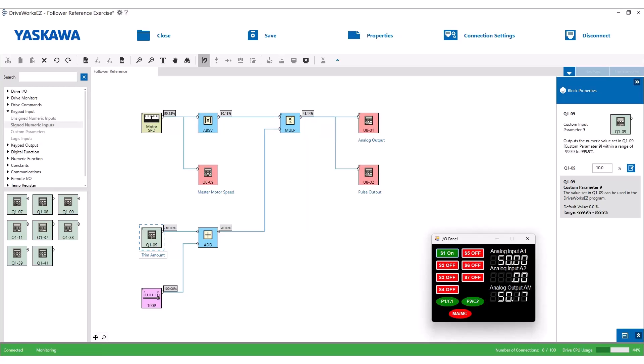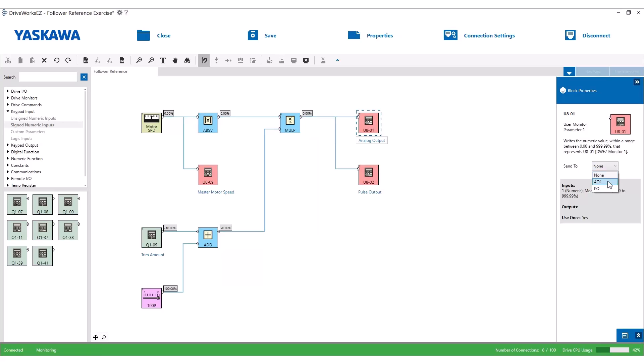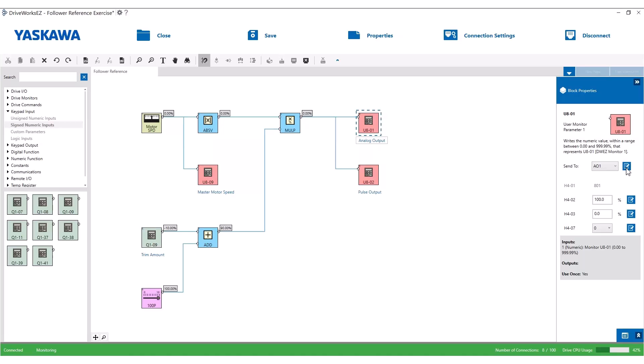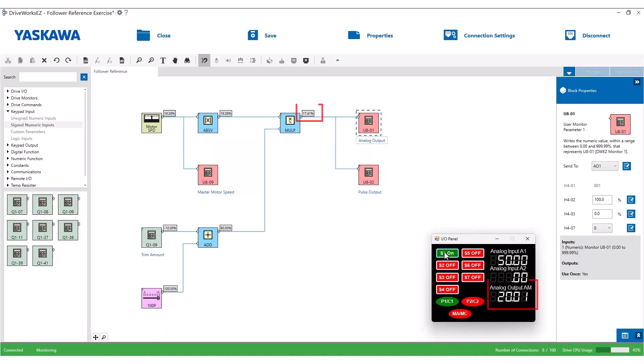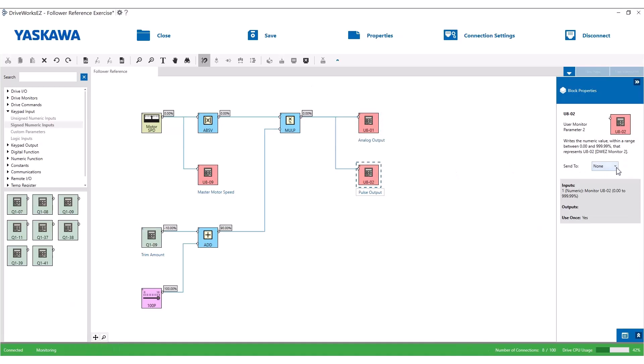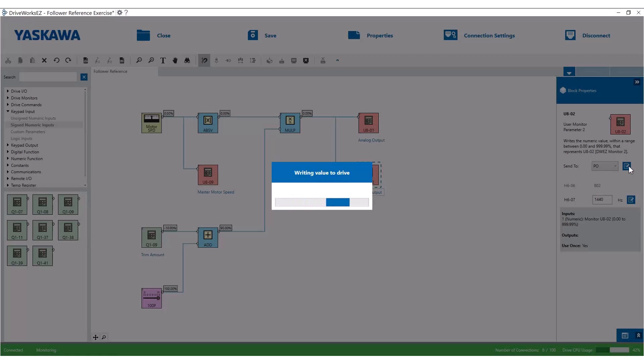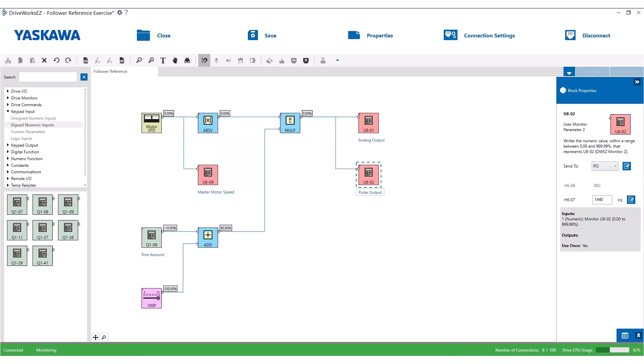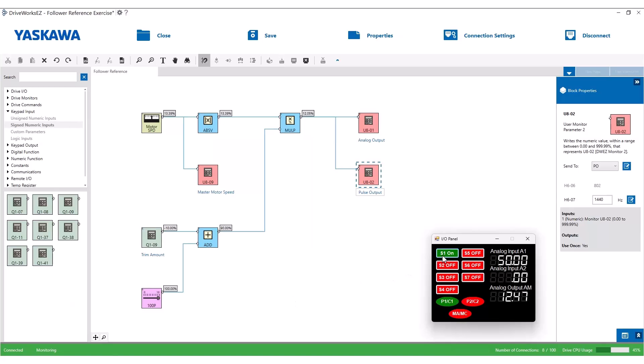Going back to the virtual I/O, you'll notice the AM is not displaying your trim speed as it should. This is because we need to program AM to work with the keypad output block we are using in the DriveWorks Easy program. Drop the run command by opening S1 — the drive will not allow you to change this parameter on the fly. Highlight the first keypad output block, check the properties box, drop down the send to box, and select the A01 setting. Write it to the drive. Now give it a run command and the AM is outputting the trimmed reference. This works great for any followers that the customer would like to wire off of the main drive. For the pulse train output, select the other keypad output block, set the send to PO, and write it to the drive. There is no MP pulse train display in the virtual I/O — whatever value the monitor block is seeing will be output by the MP terminals as a pulse train.